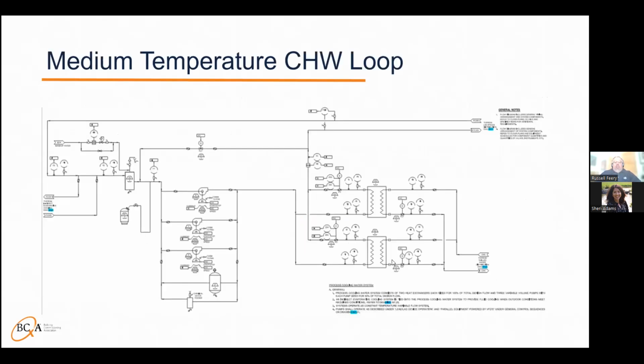You also have a medium temperature chilled water loop. On this particular project, they're running about 52-degree chilled water, a higher temperature chilled water, to avoid condensation issues and approaching dew point, so the chilled beams can't actually rain down. In this particular system, they've got a district energy loop and some heat exchangers in the building maintaining that medium temperature chilled water loop.